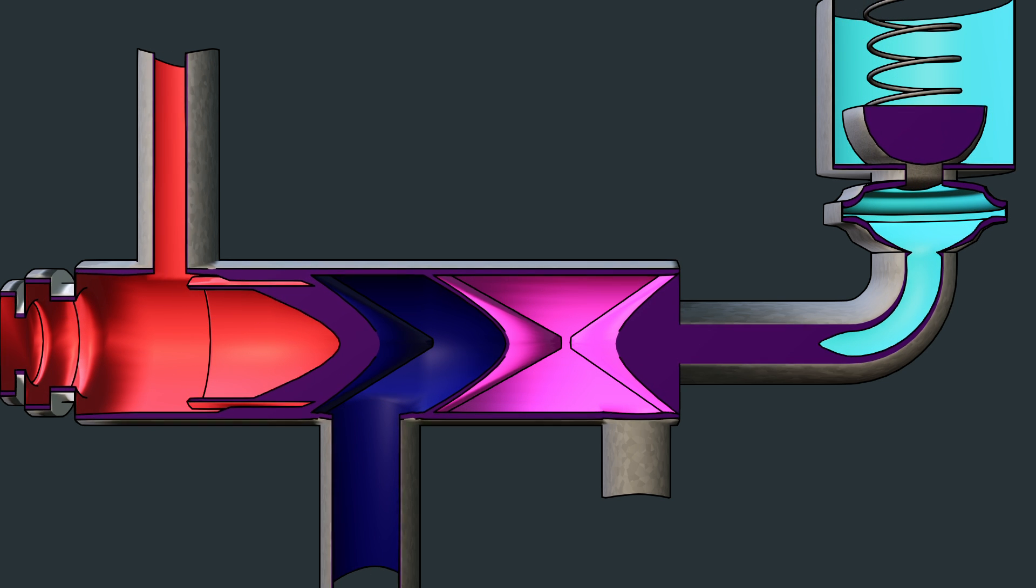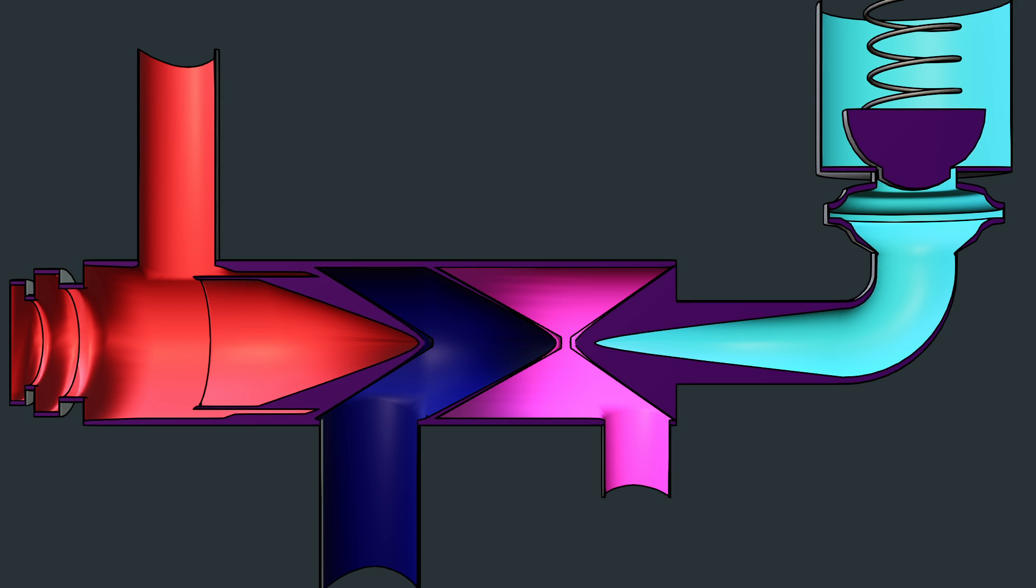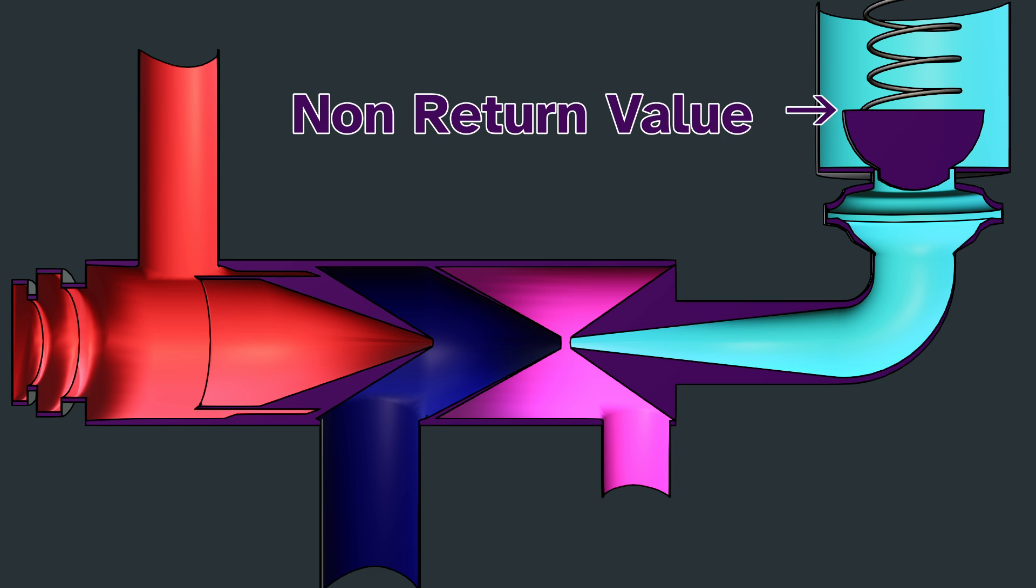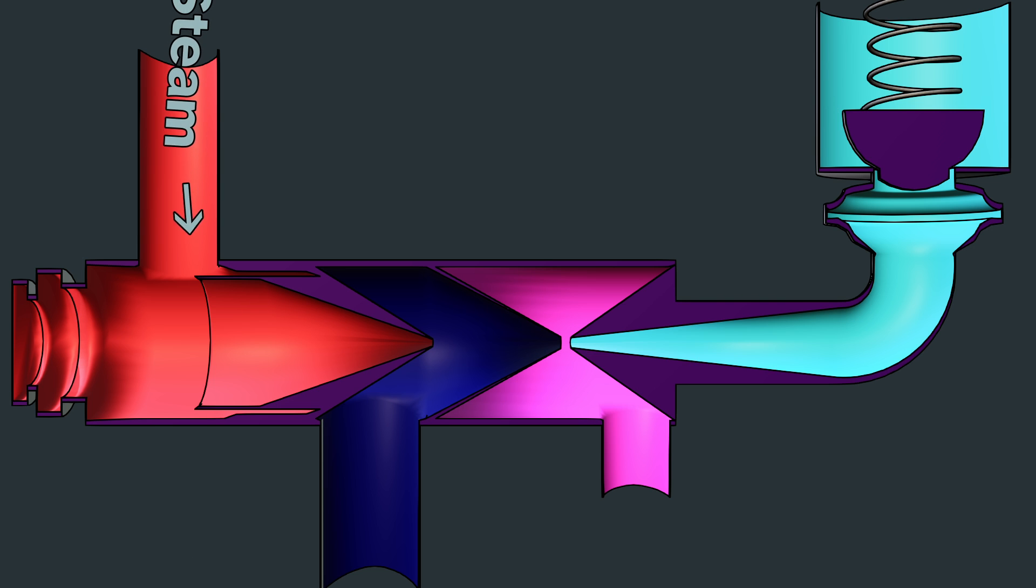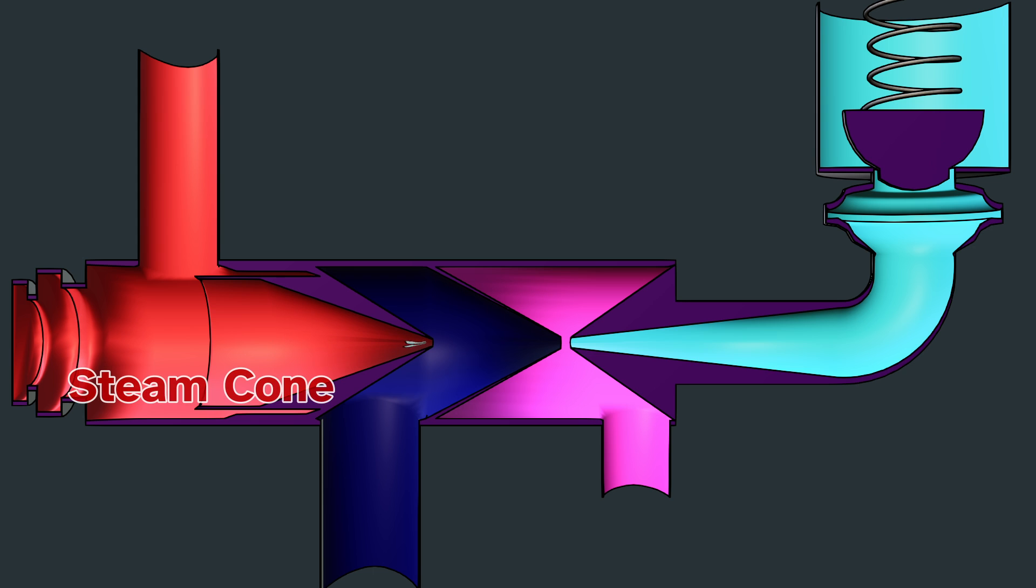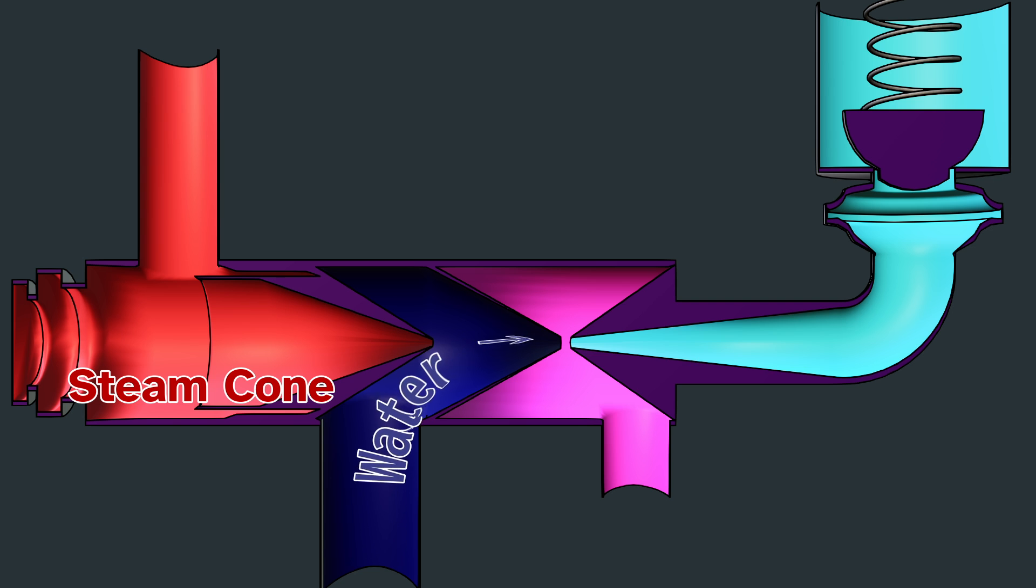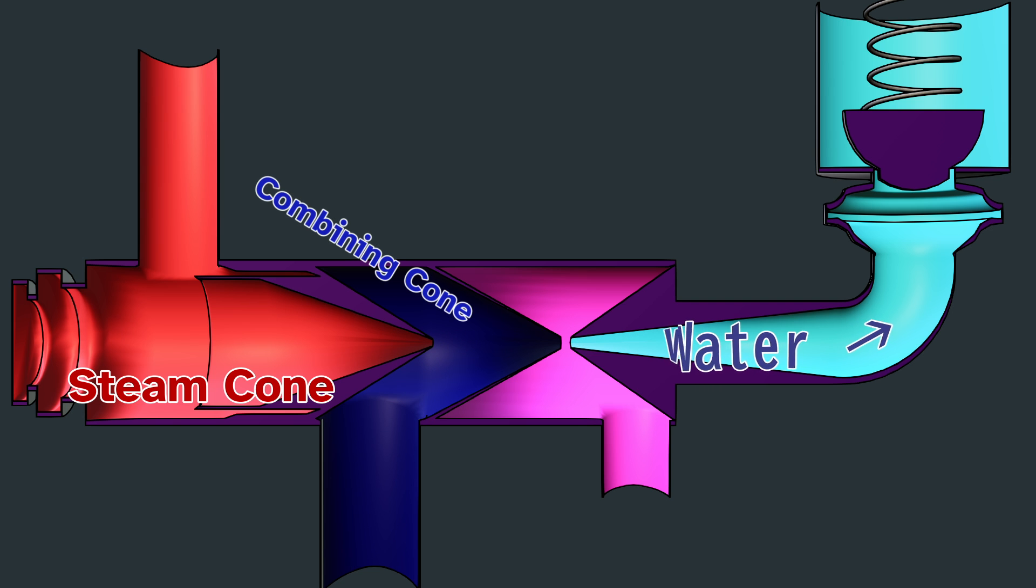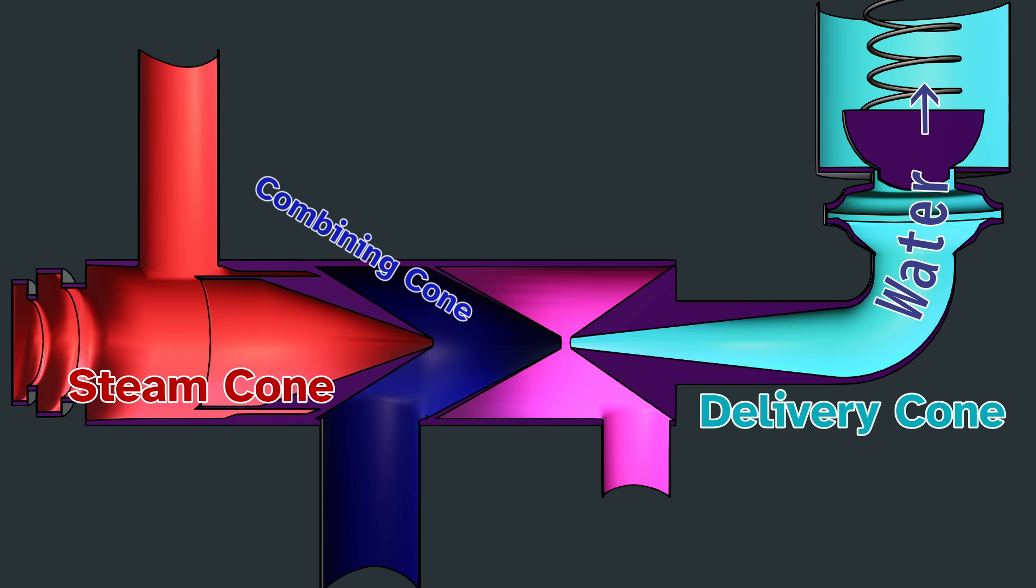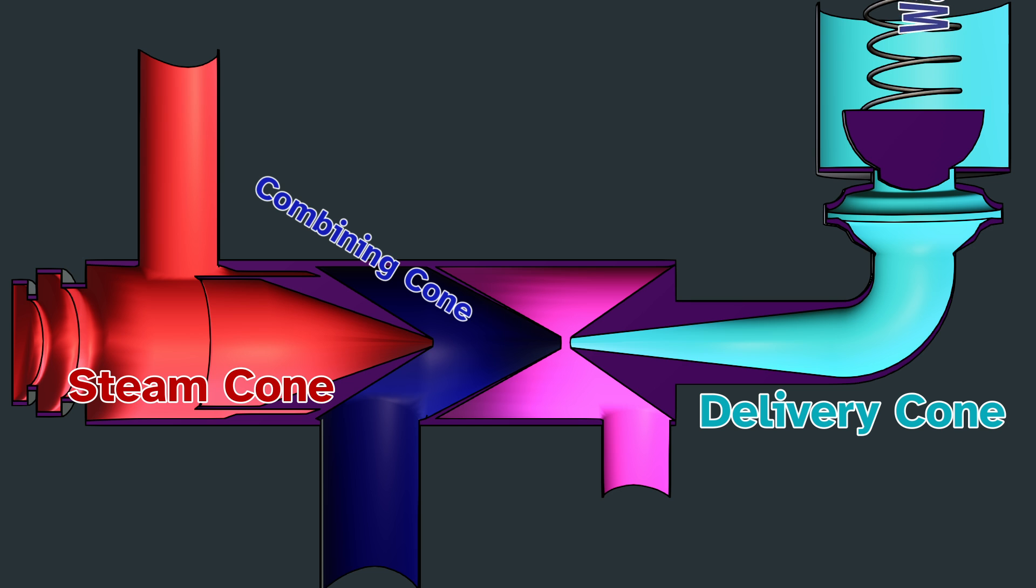This incredible device has only three moving parts: a non-return valve, the steam, and the water. High-pressure steam flows in here, and then it is constrained by this cone called the steam cone. Water is sucked up through this pipe and is combined with the steam in the combining cone. The water is then delivered to the boiler by the delivery cone. The water pushes through this one-way valve and into the boiler.